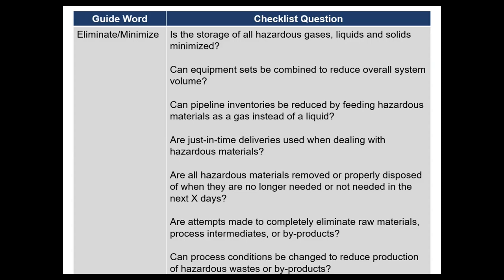Here are examples of elimination or minimization checklist questions for your HCA. These can be rephrased to prompt maximum creativity, such as using 'how might it be possible to do the following?' rather than 'is this possible?' Questions include: Is the storage of all hazardous gases, liquids, and solids minimized? Can equipment sets be combined to reduce overall system volume? Can pipeline inventories be reduced by feeding hazardous materials as a gas instead of a liquid? Are just-in-time deliveries used for hazardous materials? Can process conditions be changed to reduce production of hazardous waste or byproducts? These questions center around minimizing in-process inventories of hazardous raw materials, intermediates, and finished products.